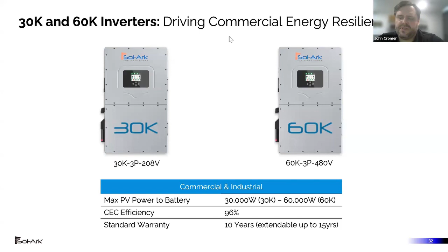As far as our system sizes go, just keep note that we scale it back for the outdoor installations, and then you can really ramp it up for indoor locations. So with outdoor, we want your projects to be successful. We want to kind of keep it simple with the provided hardware, the provided bus bars. So it's basically, you can go up to 6 inverters with a minimum of 1 battery cabinet per inverter, up to 6 battery cabinets per inverter.